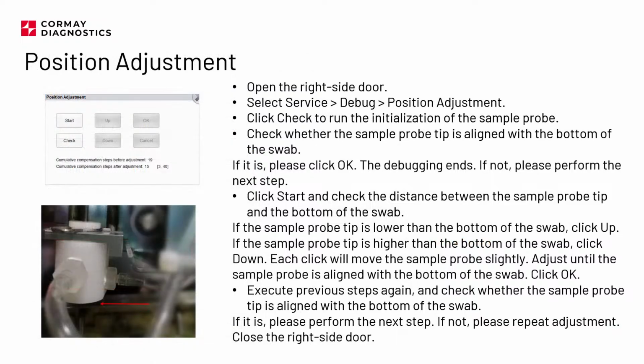Another thing which should be checked, but is not necessary to adjust, only if needed, is the sampling needle position in the rinsing head, or we call it swab. During the normal operation, basically the end of the sample probe, the tip of it, should be at the bottom of the swab or rinsing head. So if you see that it's in the middle or is extending, right, going out just a little bit from here, you will need to make this adjustment, and this is the menu which allows you to do that, right? There is a start, the analyzer will make an initialization, and then you can use up and down to go up and down. And what you need to do is to align the tip of the sampling needle with the end or the bottom of the rinsing head, right?